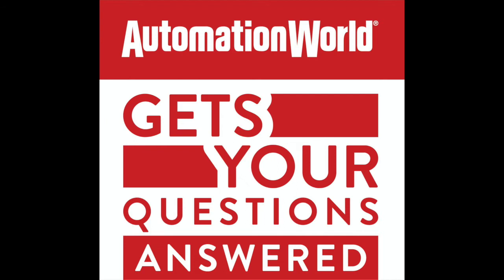On the operations side, I would say it's interesting to think about how MTTR ties into other more operationally focused metrics like OEE, one of the subjects of your podcast in the past, right? So if you are improving your MTTR, you should see that reflected in a higher asset availability metric and then a higher OEE score, right? Because that means when you go down, your faulted time is hopefully being minimized because you're able to repair it quickly. Therefore, your OEE score should be higher.